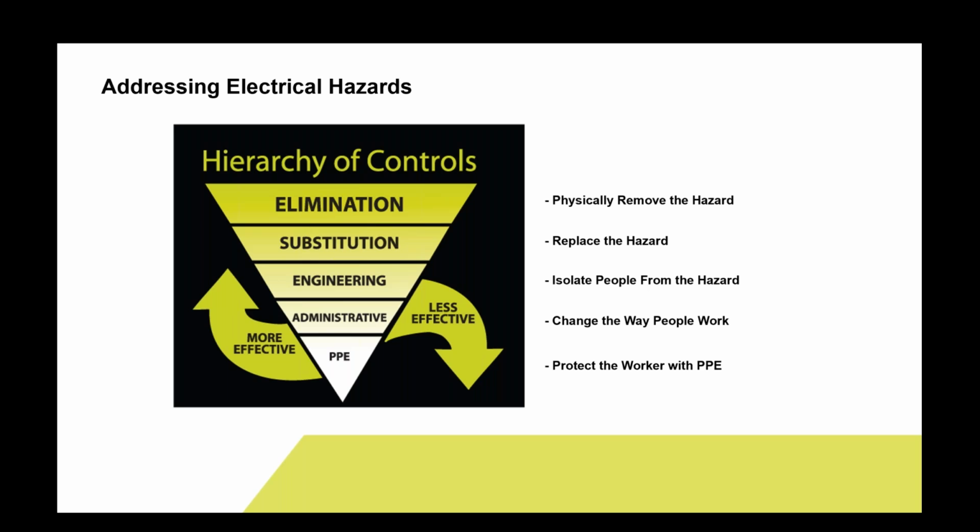And I think that, specifically with regard to racking circuit breakers and incident energy, if you're in front of a breaker within 2 or 3 feet where you have a manual racking tool in your hands, all of those hazards we mentioned earlier about light and sound, molten copper, right? Even before we get to the heat, which is what typically your PPE is picked out based on, an energy level. All those other considerations have to be looked at as well. So what we're trying to do here is say, okay, let's go to the hierarchy of controls and figure out what can we do to address incident energy?